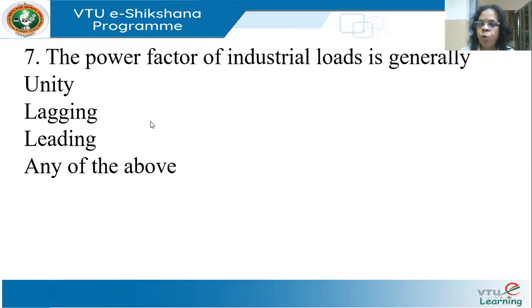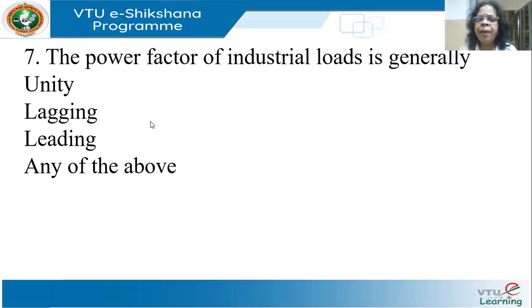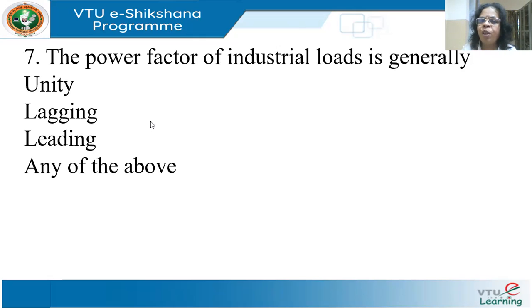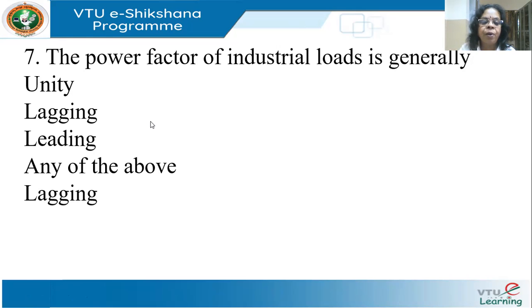The power factor of industrial loads is generally: unity, lagging, leading, or any of the above? Unity power factor applies only to purely resistive heating loads. Leading power factor would require intentional capacitor banks. The correct answer is lagging, because most industrial loads — electric motors, transformers, welding plants, discharge lights, air conditioners — are all lagging loads.